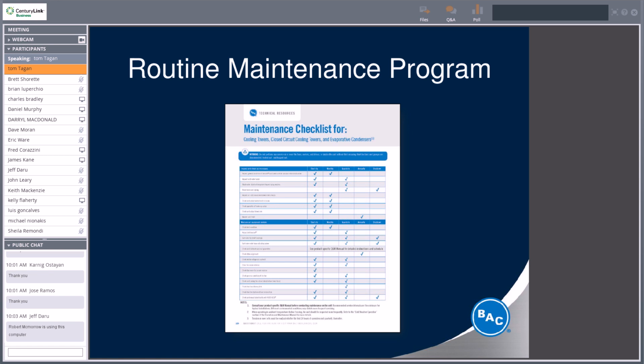Again, I realize this is really small and hard to see, but first and foremost, inspect the general condition of the unit and check the unit for any unusual noise or vibration. Real easy to see, your initial inspection of the cooling tower is to make sure there's no leaks and that it doesn't sound funny. If you've got any excessive vibration or any odd noises, you may have a fan out of balance, a belt that needs to be tightened, a gear that may be out of alignment, or some bearings that are starting to go. So, first and foremost, look and listen.